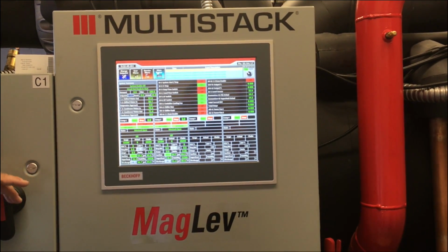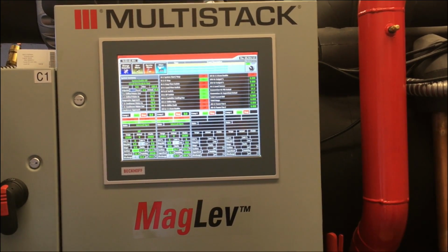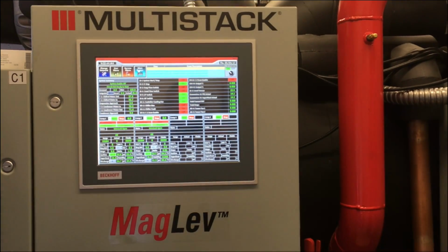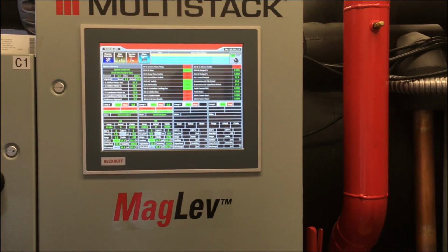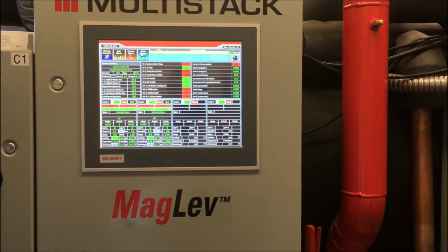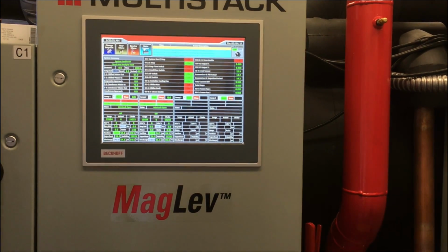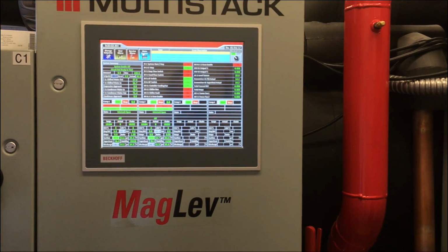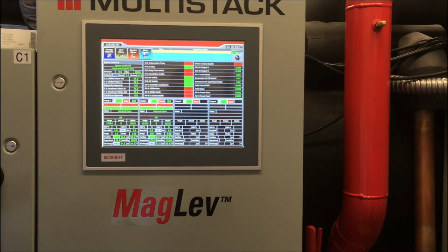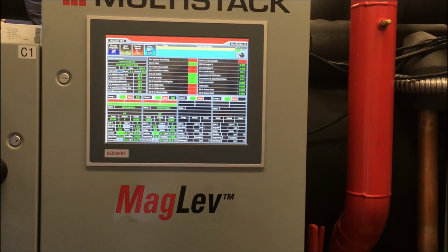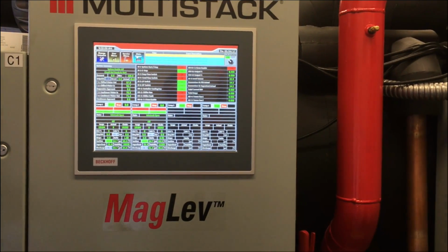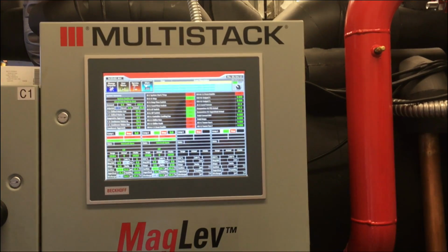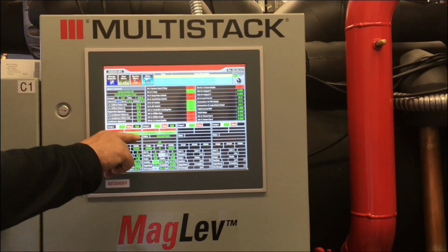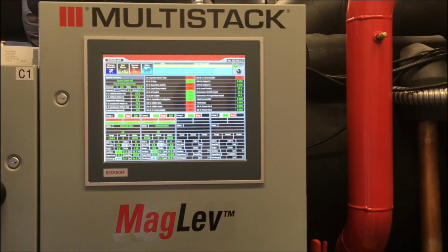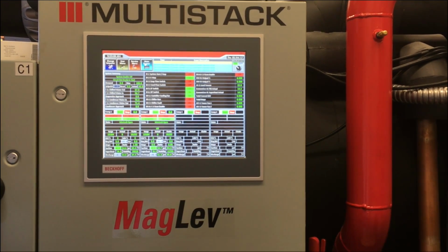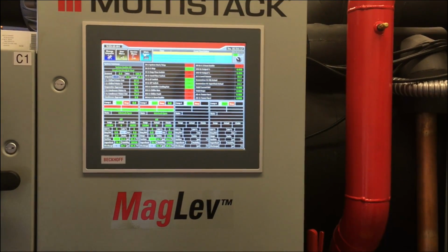But if you got 3, say, high temp inverter, because your cooling tower was 45 degrees, because somebody tried to run this in February, and what happens is your chill water's at 70 and your cooling tower's at 45, we're in what's called inverted. We can't build a pressure ratio. So if we can't build a pressure ratio, we can't cool the compressor. So what happens is that it'll go off on like internal temperature. If it does that same one 3 times in a half hour, right here it'll say compressor lockout. And the only way to clear a compressor lockout is to kill its power for 3 minutes roughly.